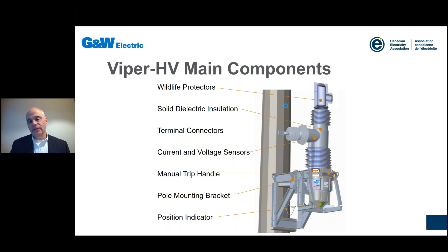Here, and it basically gives you a little bit more of an X-ray view. It's a vacuum interrupter technology that's utilized here. That is a single vacuum interrupter that's rated all the way up to 72.5 kV.